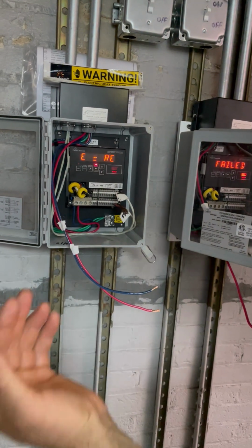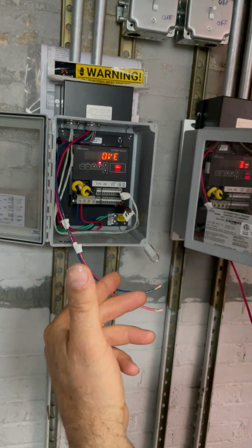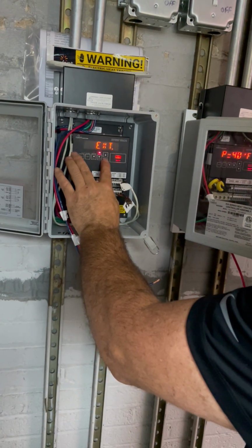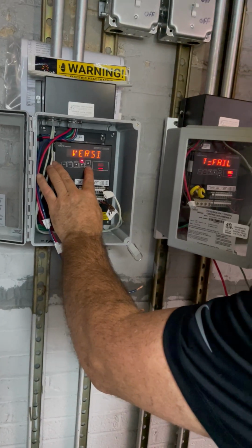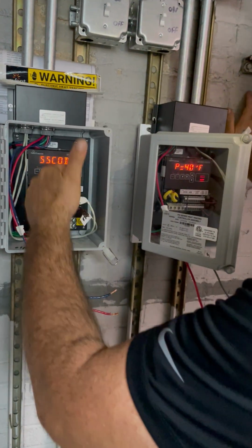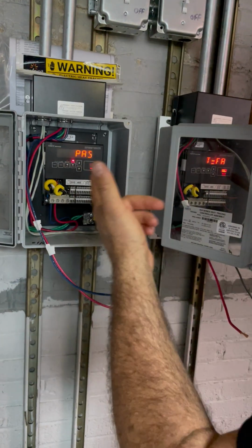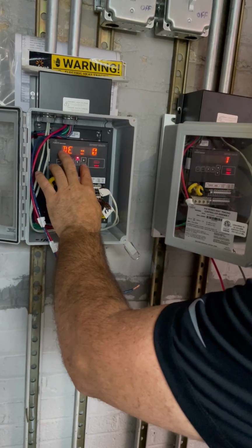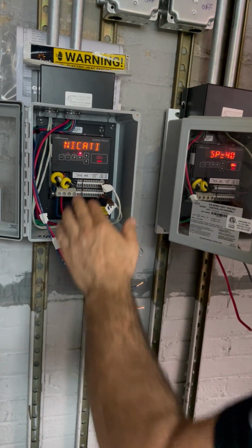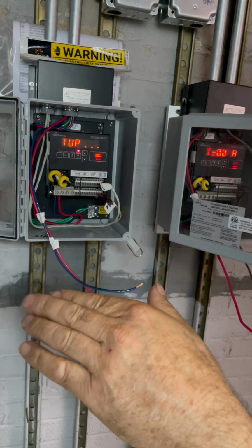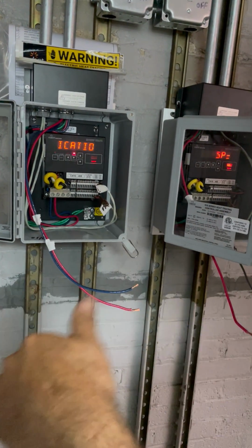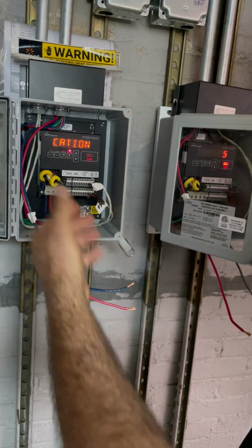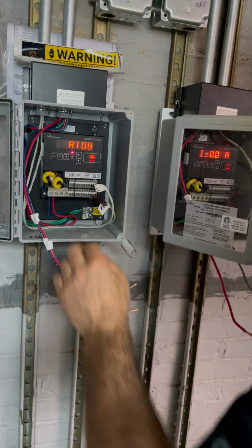Override. This has a capability that you could have an external source turn it on, and there are any number of reasons you might want to utilize that. There's a whole bunch of communications and things. You could put a passcode on here if you don't want somebody messing with it. I strongly suggest you do not do that because it's in a secure location anyway. It's not going to happen. It has abilities to talk directly to a computer via Modbus or through a translator to BACnet. Again, I would just look for the closure of the contacts and do that.